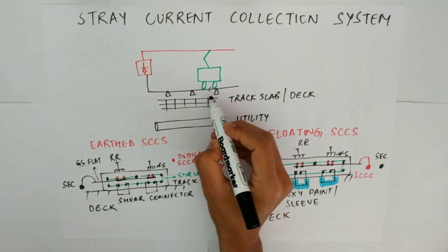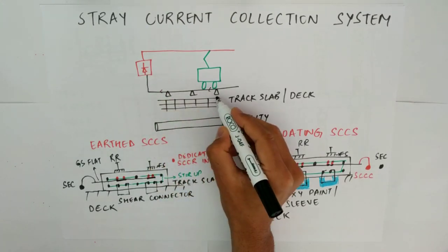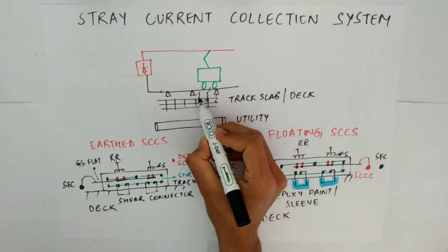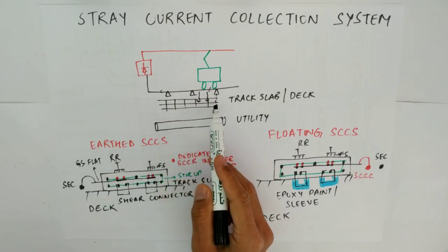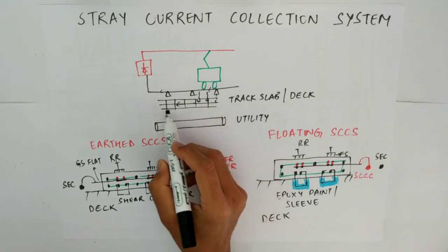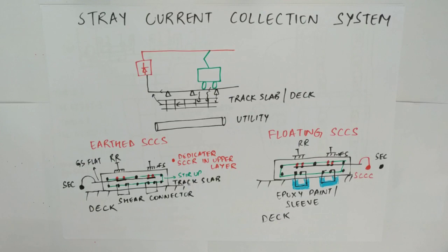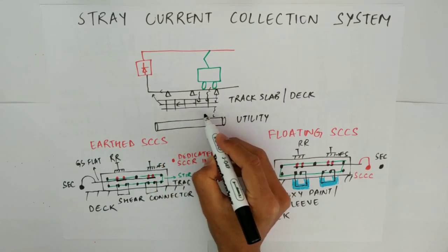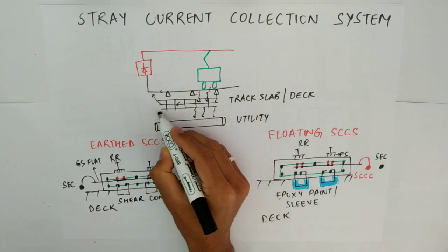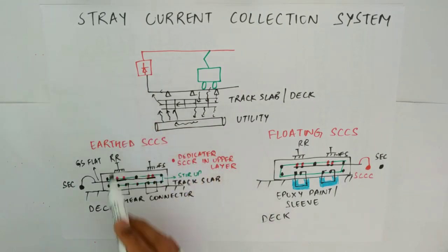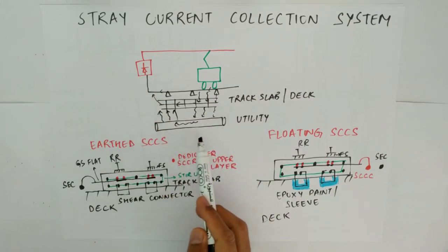When the return current is going back to its source, due to some imperfections in the insulation there is some leakage. The current will enter into the track slab or the reinforcements available below, and from here the current will start moving and then eventually enter back to the running rails and go back to the source. But even after this mesh there can be some leakage if there is a low resistance path available below, and from this path the current will try to travel and go back to its source — which can be your gas pipelines, water pipelines, or other utilities.